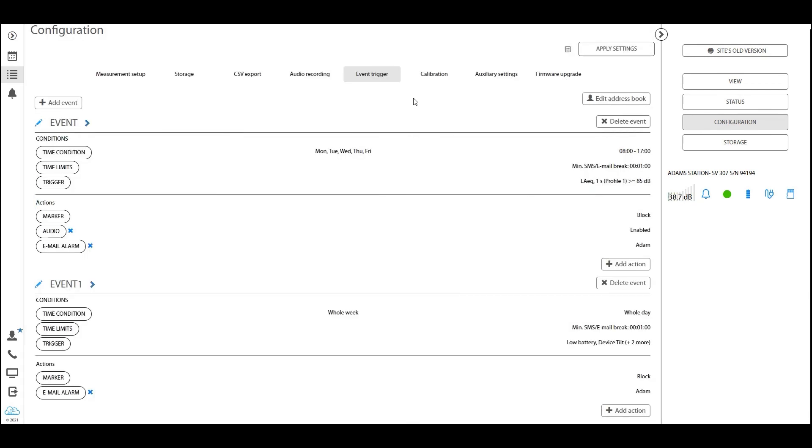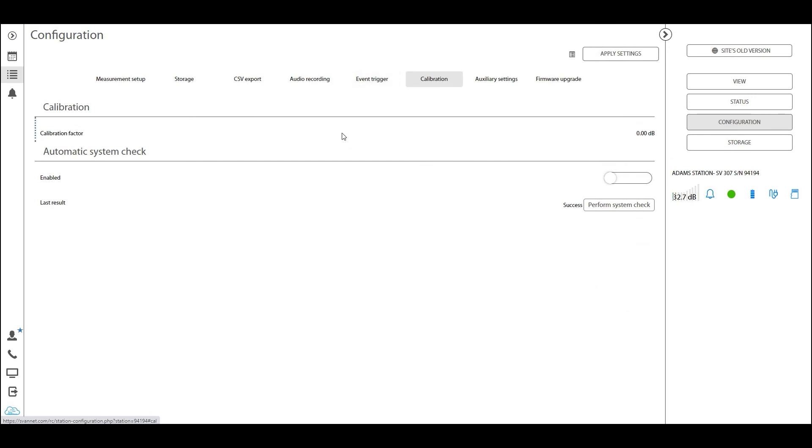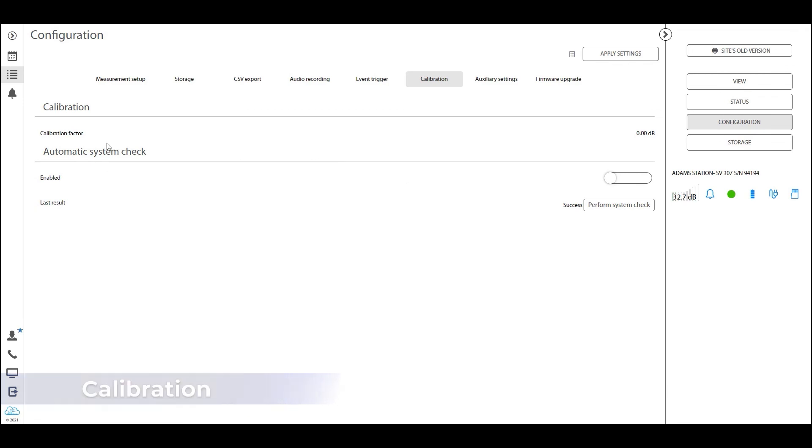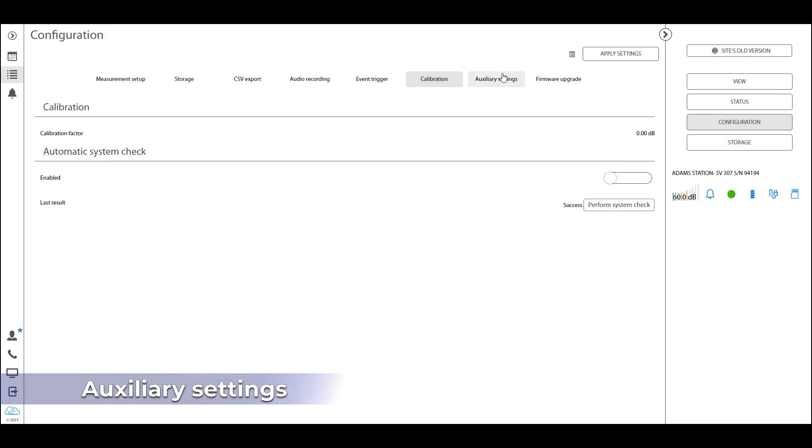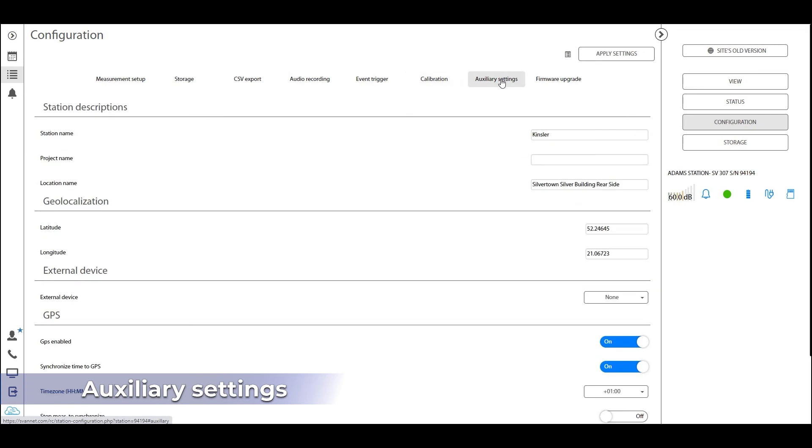The last two tabs I'd like to go through is the calibration tab. Here you can activate a system check for your device as well as check the latest calibration factor that the device saved. The system check is the sound source that is on the 307, and this is only available for the 307 and the 200a.